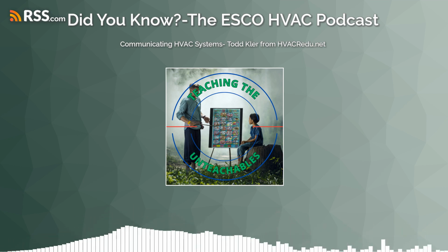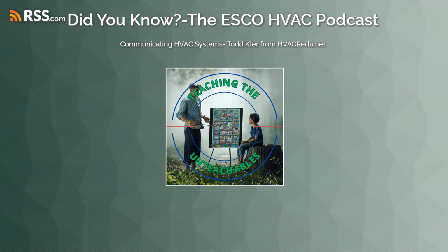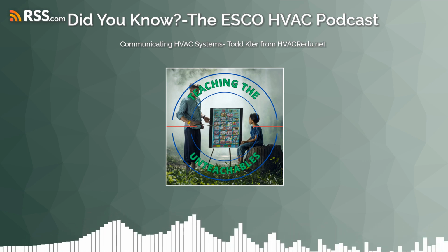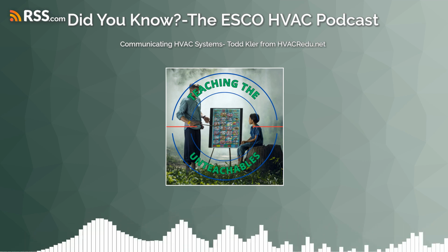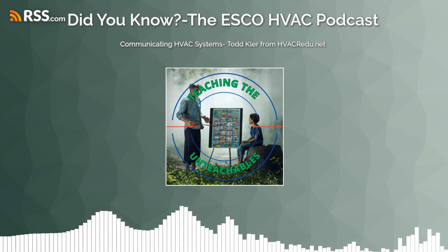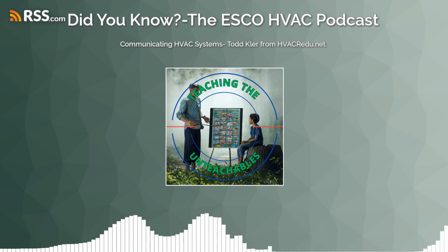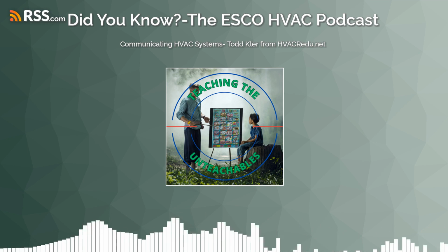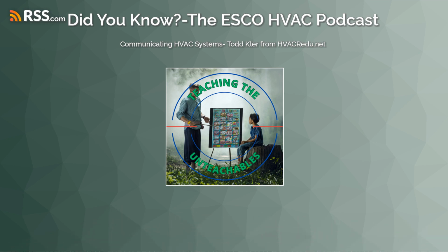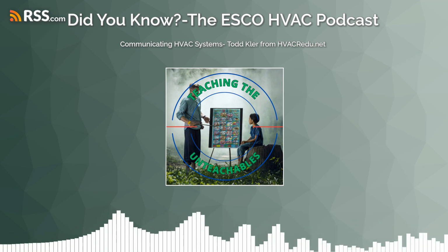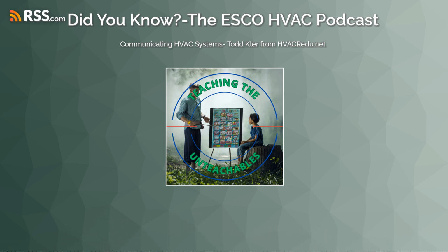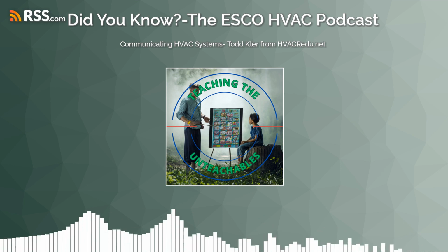Yes. So worst case scenario, disconnect all your wiring. Check it. Make sure we got our 2.8, 2.2, or our 0.6 bias difference at our indoor unit. It's going to be 1.9 and 1.3 on an air handler, but it's still a 0.6 difference. And then start adding my parts. When I add something on and my voltage bias changes, guess what? 0.6. If it's not, I've just found my problem.